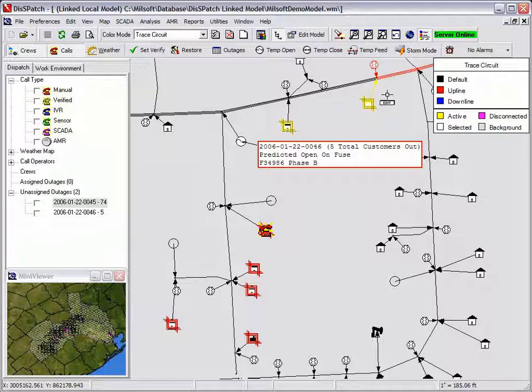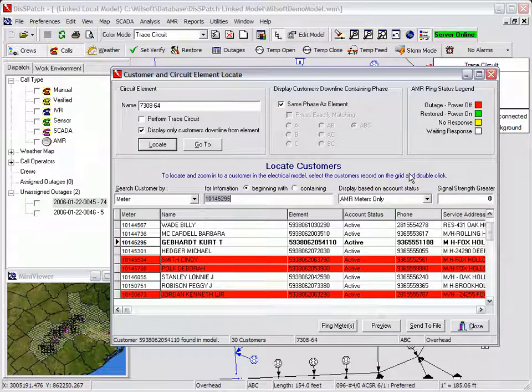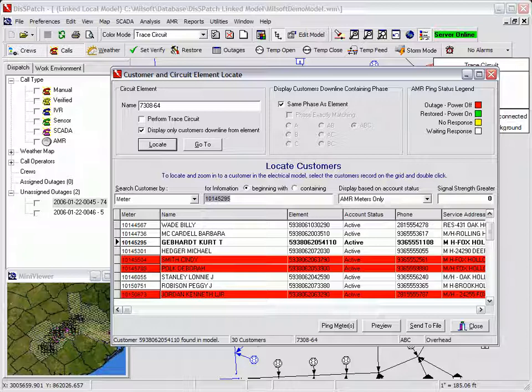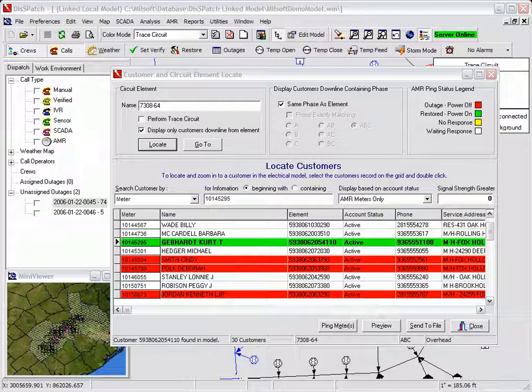The dispatcher then selects the three-phase overhead line section upline from the device and selects the locate option from the speed menu. The customer and element locate dialog displays just customers downline from the selected line section. The records change color based on the status reported from the AMR system.